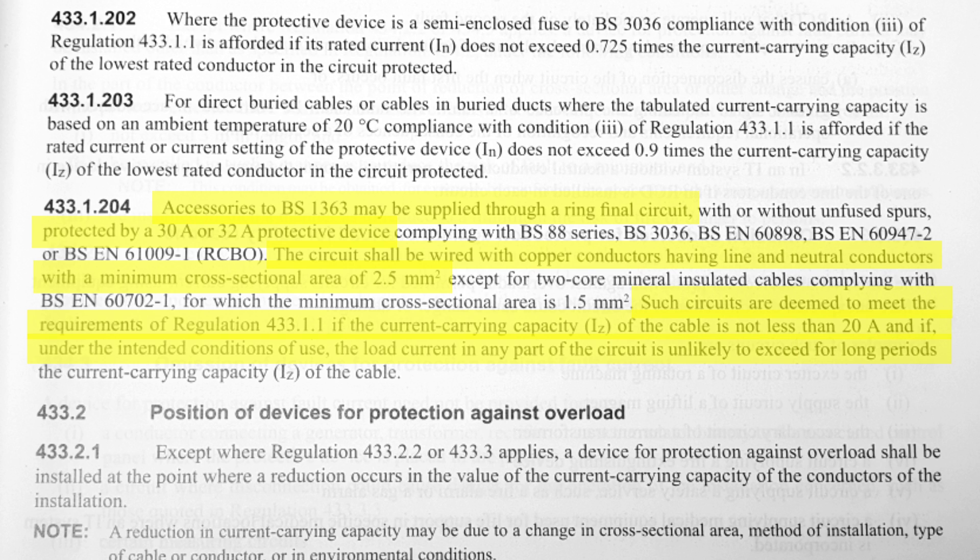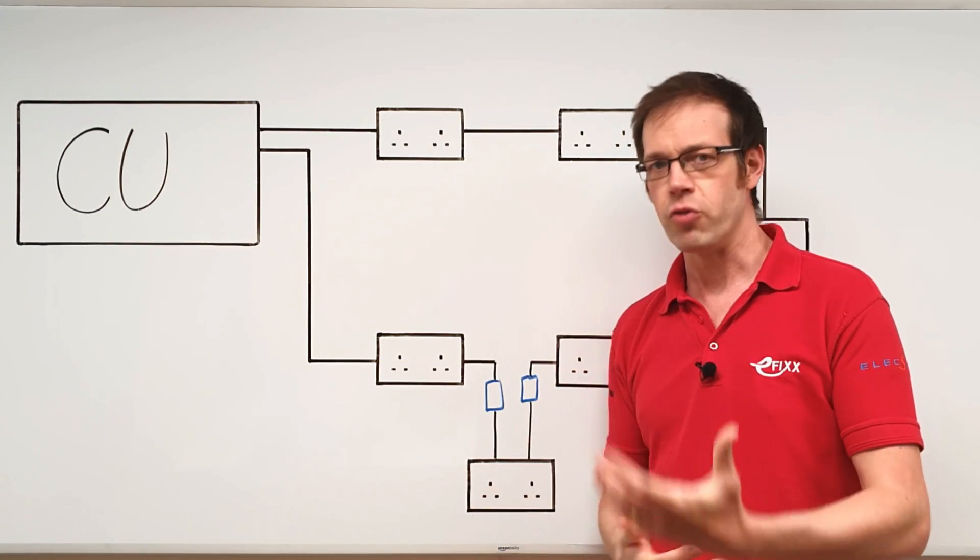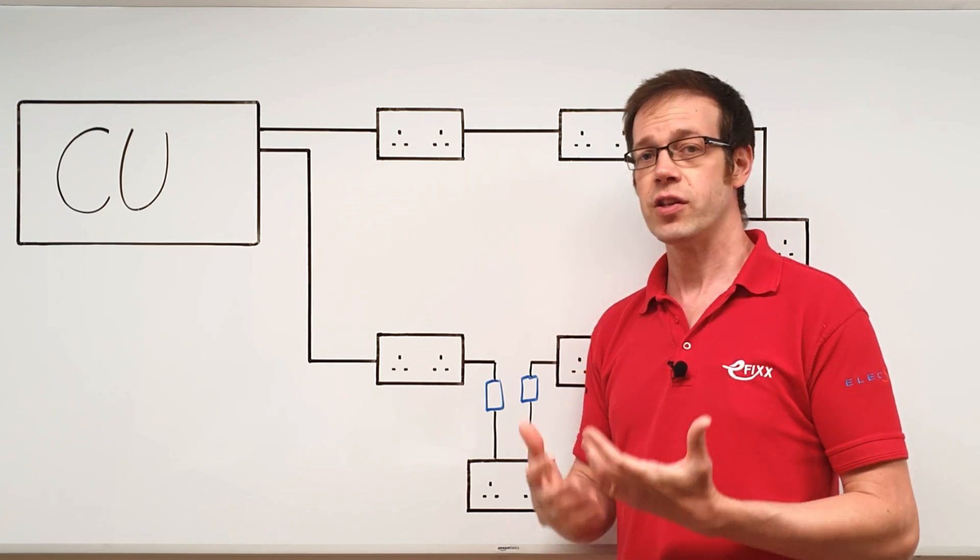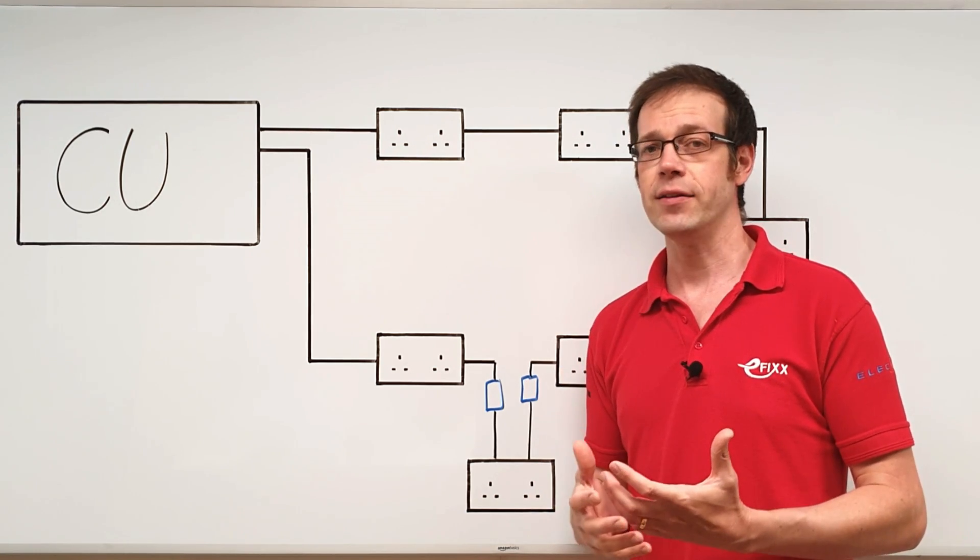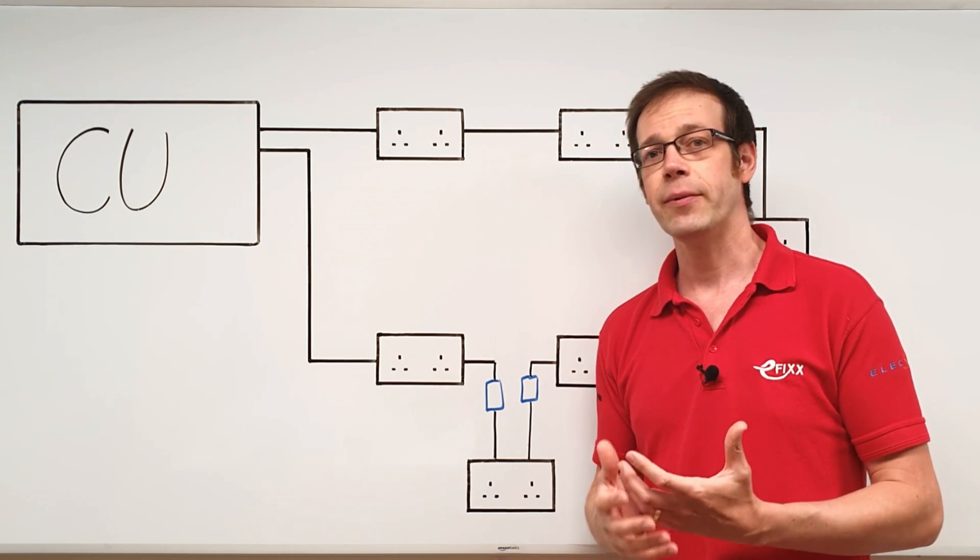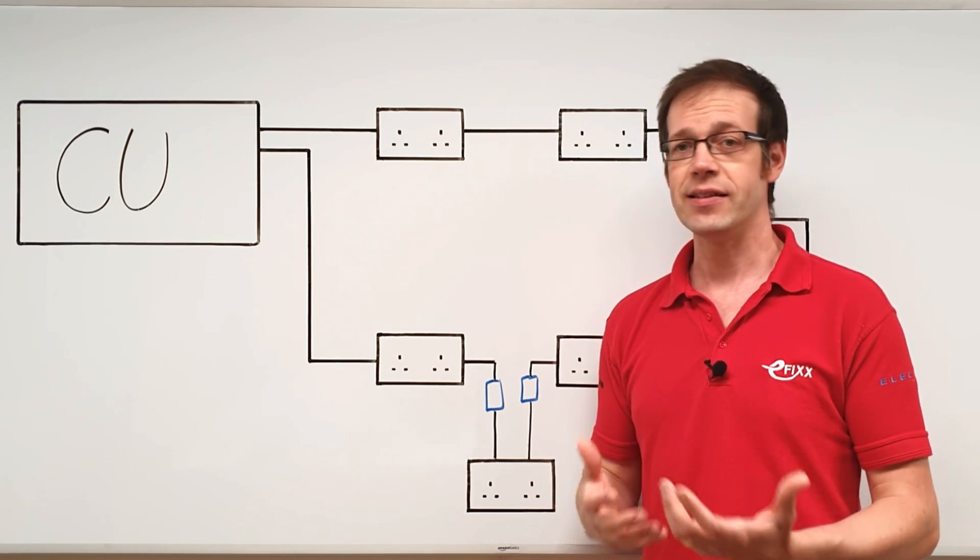So let's unravel that. What it's basically saying is that as long as the loading on the ring isn't expected to be ridiculously unbalanced, the cable needs to be able to carry at least 20 amps under normal conditions, as it's unlikely that the current flowing through any part of the ring will be higher than that.